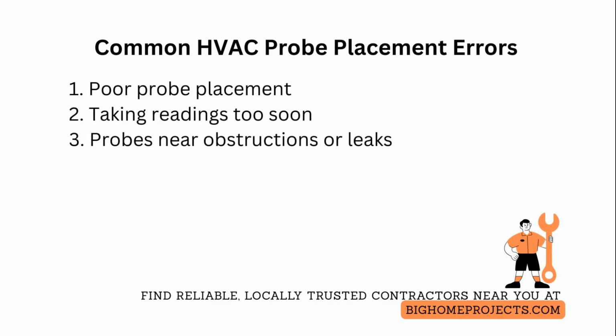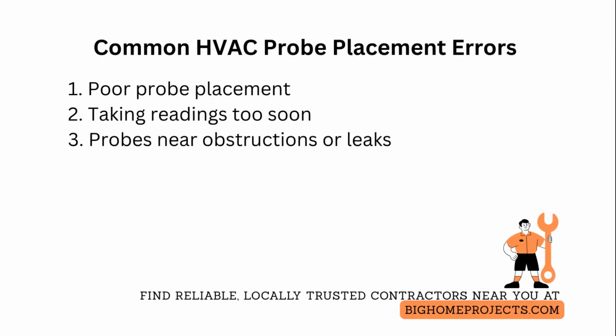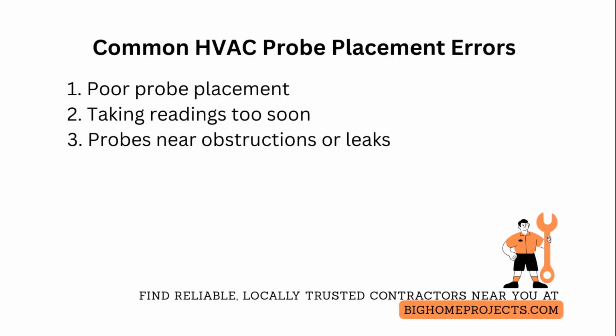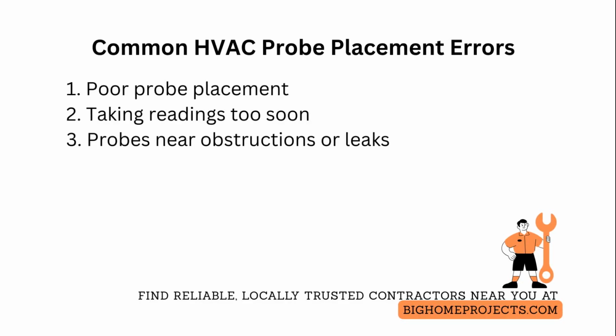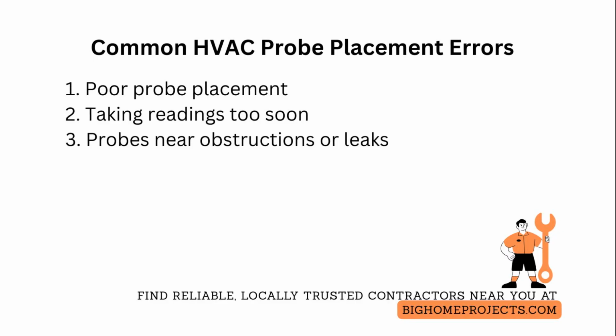One of the frequent errors is using probes in obstructed locations or near leaks, which skews the temperature delta and CFM. Fix this by choosing straight-run sections at least 1 to 2 duct diameters from fittings, sealing probe ports with high-temperature silicone, and, for non-circular ducts, averaging multiple points.